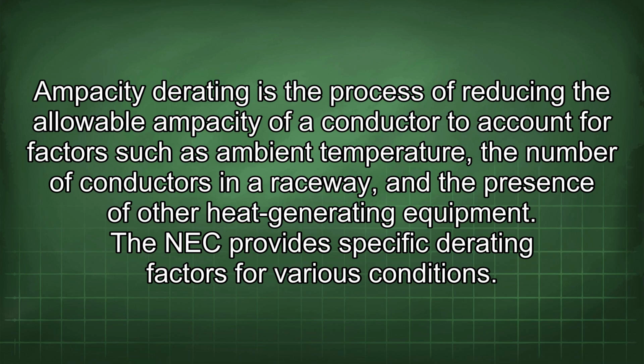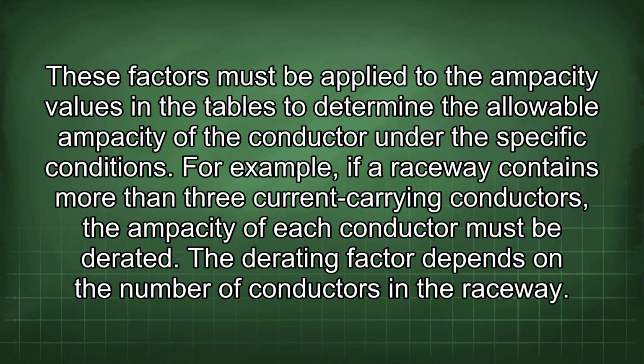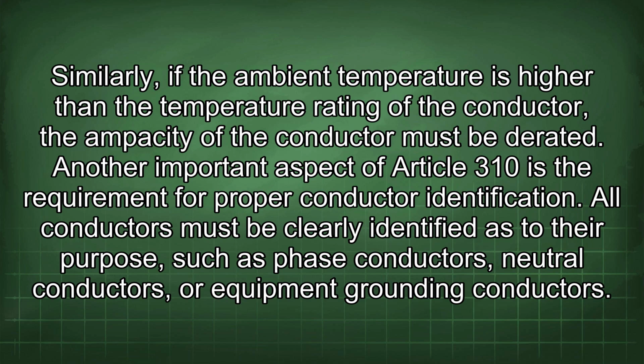The NEC provides specific derating factors for various conditions. These factors must be applied to the ampacity values in the tables to determine the allowable ampacity of the conductor under the specific conditions. For example, if a raceway contains more than 3 current-carrying conductors, the ampacity of each conductor must be derated. The derating factor depends on the number of conductors in the raceway.